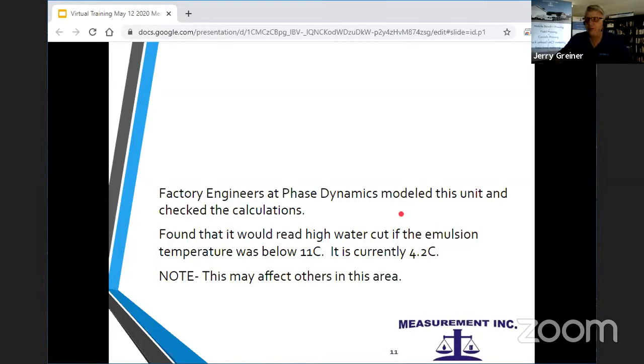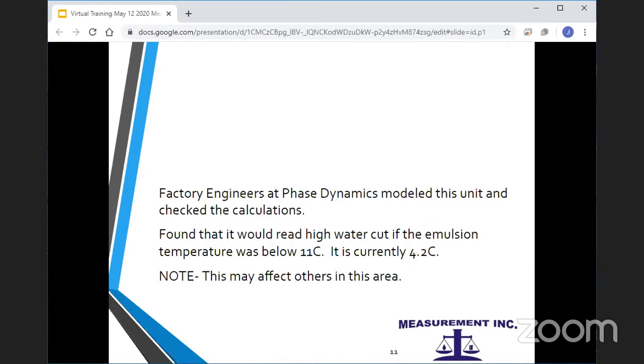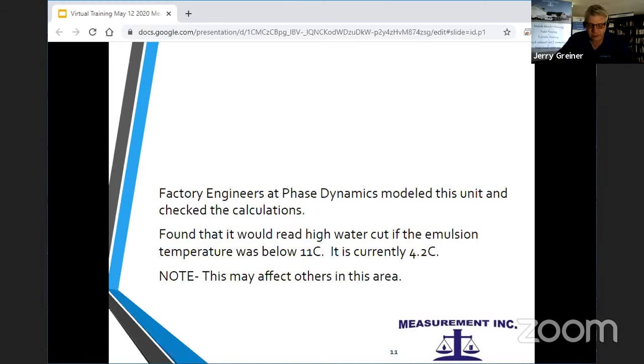When they first did it, everything worked perfect on it, they said, and there was nothing that was out of order in it at all. Everything was working perfect. And then he says, well, wait a minute, I'm at 15 degrees Celsius. What's your temperature there? And when we told him that it's running at 4.2 Celsius, he couldn't believe it. They're from, I think, Texas or California. I'm not exactly sure where they are, but they're southern United States anyhow. And he couldn't believe that we would have any oil that gets that cold. And we're like, well, it's winter time and it's Canada and it's cold. And 4 degrees C is really not uncommon at all. Lots of times it's probably below 0 Celsius in shipping tanks. But there was that error and it might affect others.